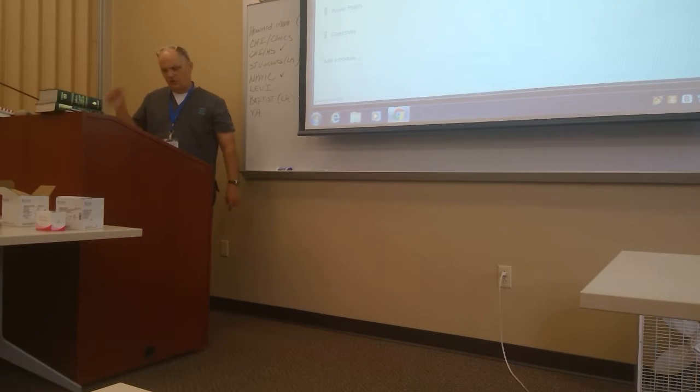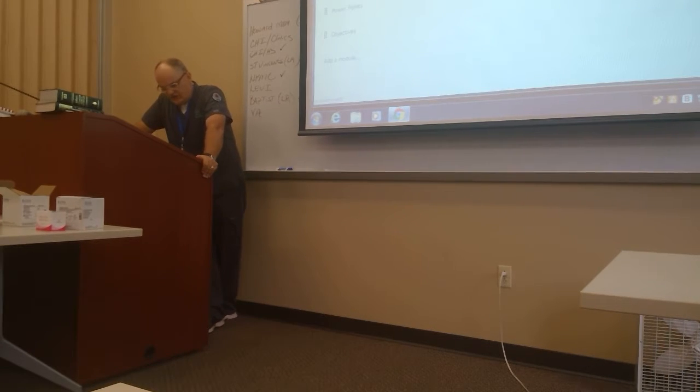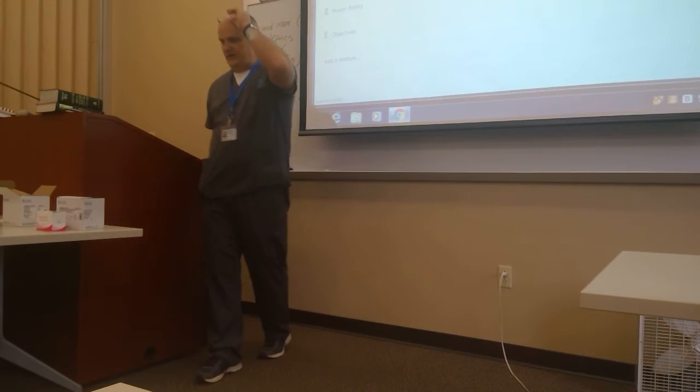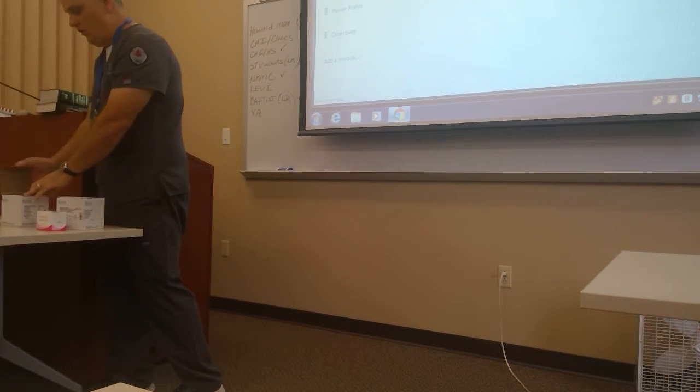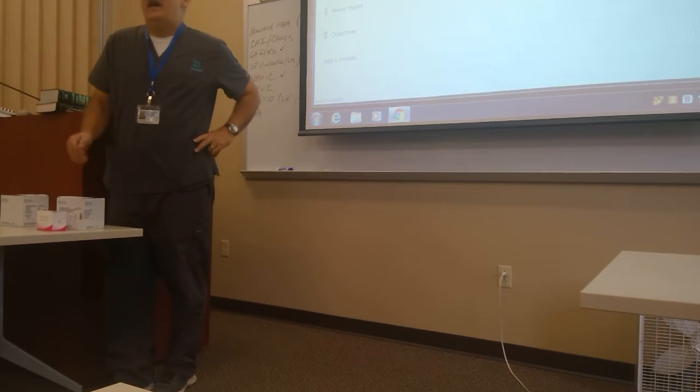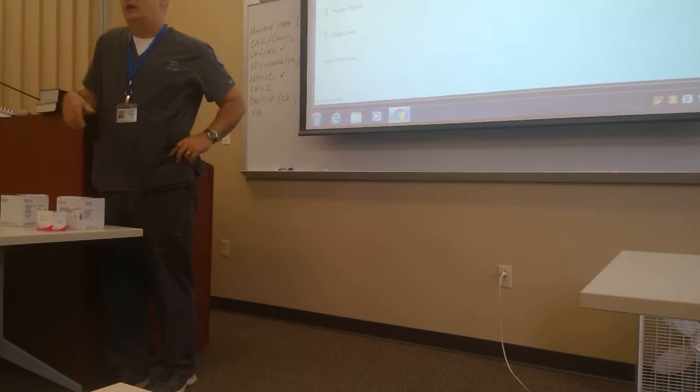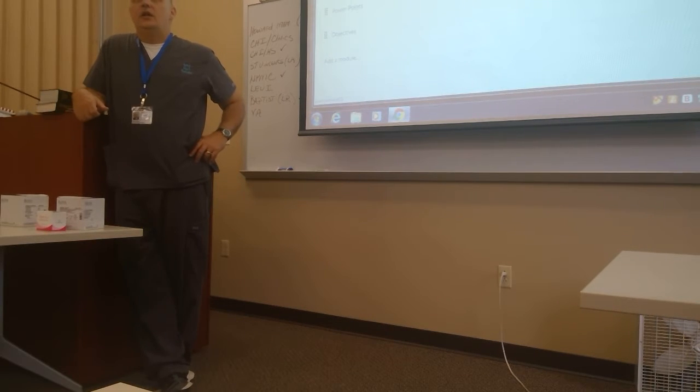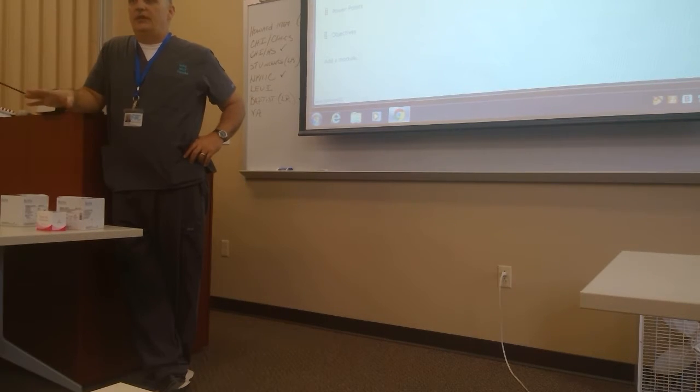Proficiency testing or external quality assessment testing. Proficiency testing is the testing of unknown samples received from an outside agency and provides unbiased validation of the quality of patient test results. Okay, so this has nothing to do with external quality control. What this has to do with, if I am a company called CAP, the College of American Pathologists, and Haley Hawley is the lab director at National Park Medical Center, for her lab to be accredited, she has to participate in what's called CAP surveys.